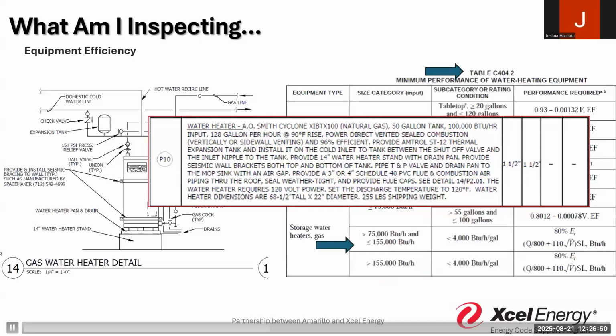Same thing with these different water heater expectations. The code tells us water heaters have to have a certain efficiency rating, whether multifamily, commercial, or under the residential provisions. I'd be surprised if, after identifying in the plan a 50-gallon tank doing about 100,000 BTUs and 128 gallons per hour, I show up on site and it's a 500-gallon tank with a million BTU. That's 10 times as big.